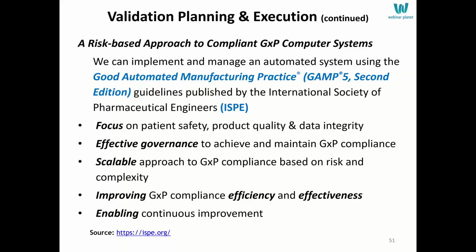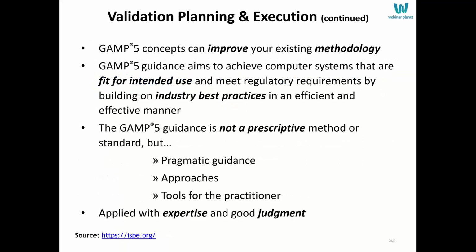But it's not required. FDA doesn't require you to follow anything from ISPE, to follow GAMP5, or to do anything that anyone gives you stepwise to execute validation. You are free to execute it the way you think it should be done. So GAMP5 can improve your existing methodology. It can show it's fit for intended use. It's based on industry best practice, but it's not prescriptive. It's not step by step. You must think about what they offer you as guidance and then apply that with your own expertise and good judgment.